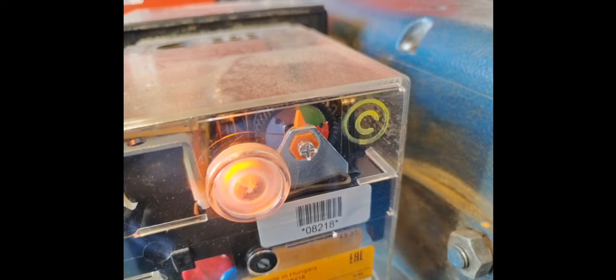The unit was locking out on lack of air. So during operation there was a lack of air. So what I had to do is increase the amount of air it had, but I couldn't increase the amount of gas. So I just increased the servo motor in order to make adjustments to increase air to the combustion in low and high fire. But the gas valve is going to need changing. But the unit stopped locking out because it started to get adequate air for combustion.